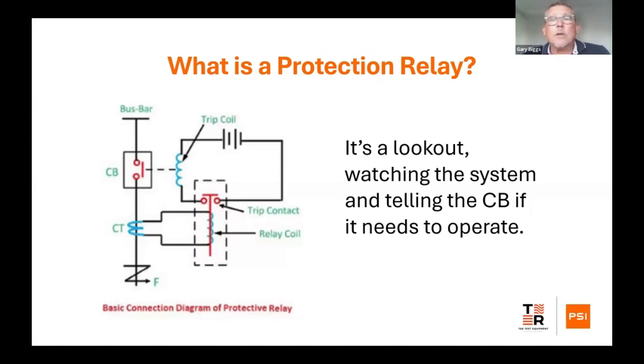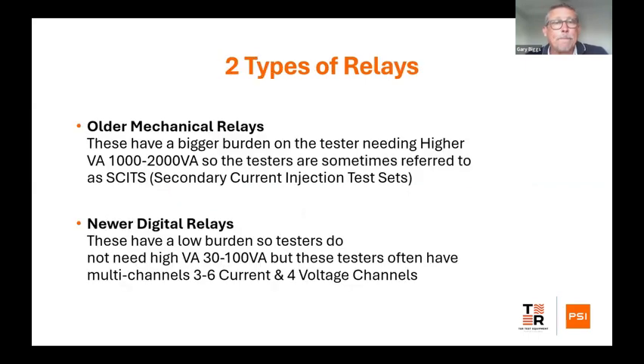So as we said, we've got a little diagram there. It's a lookout. It's watching the system, and it's telling the circuit breaker if it needs to operate. As I said, each individual relay in the old days would have a distinct function, looking at just one function. In modern times, as we'll see, it's quite different.